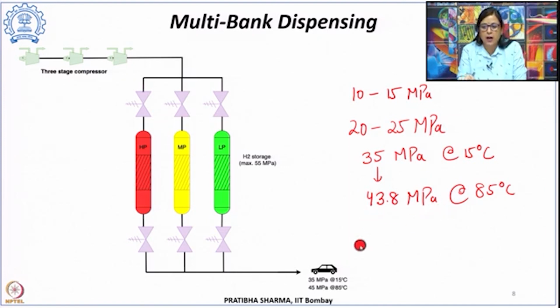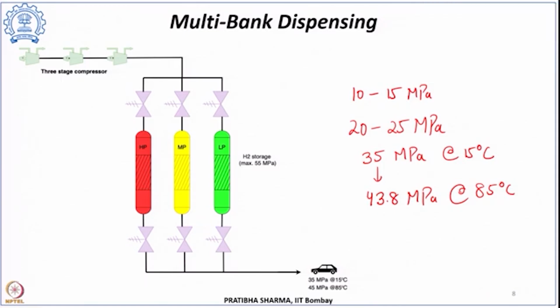That corresponds to filling at 85 degree centigrade to 43.8 MPa. Now, if the car tank pressure is 43.8 MPa, that means if it has to be filled through the high pressure bank, the high pressure bank should be above 43.8 MPa, usually around 44.8 MPa. So this is the high pressure bank pressure, roughly 45 MPa at 85 degree centigrade. This is when the car tank is meant for 35 MPa.